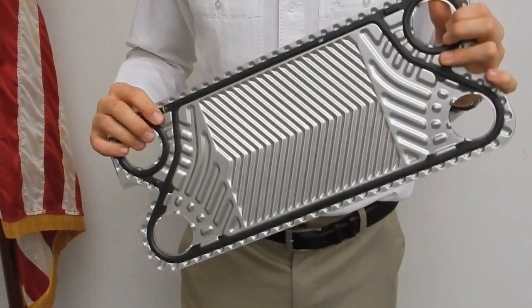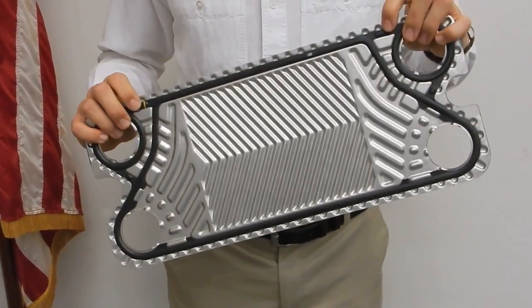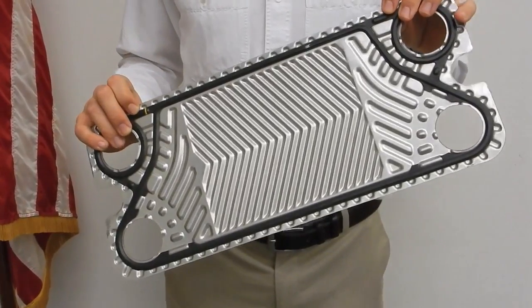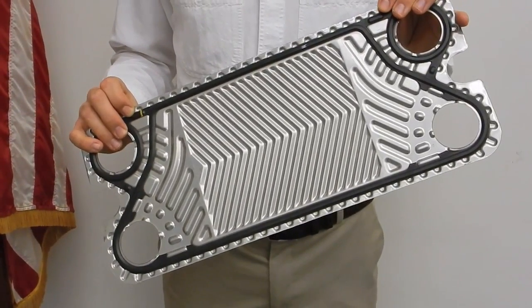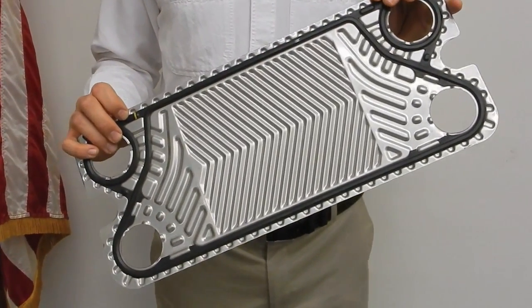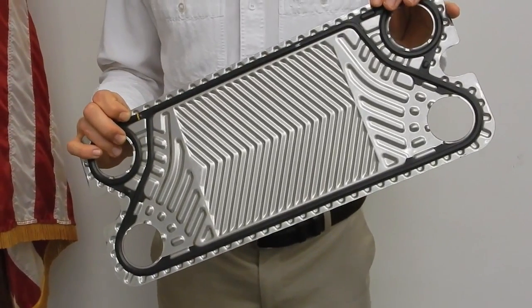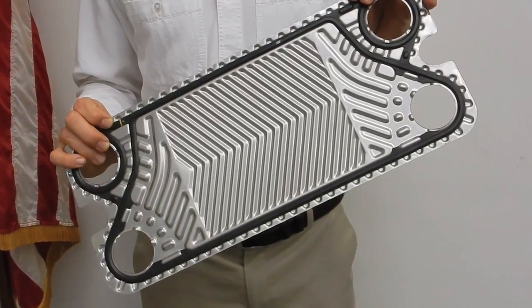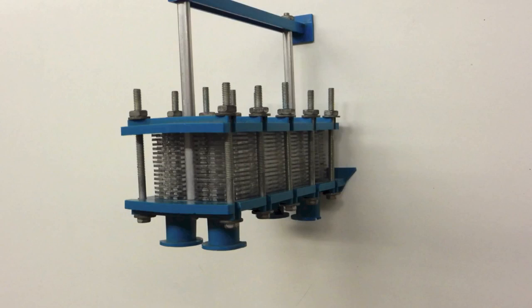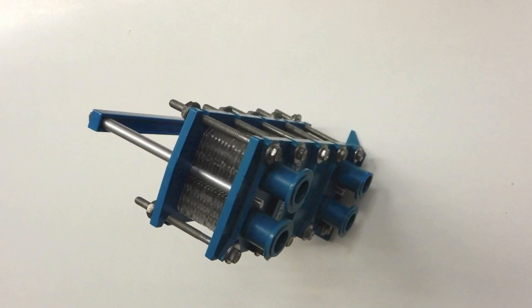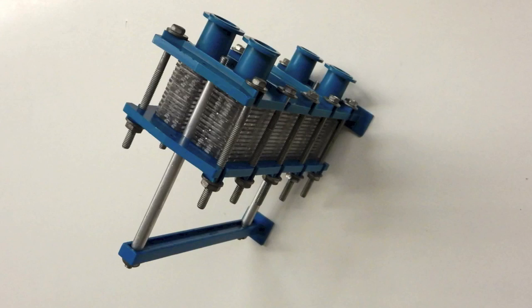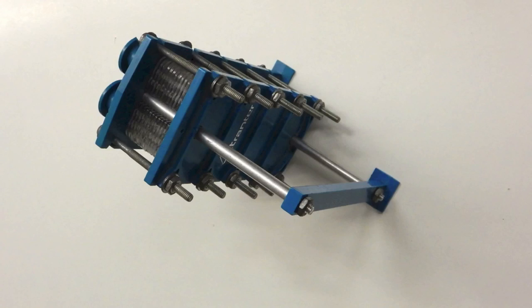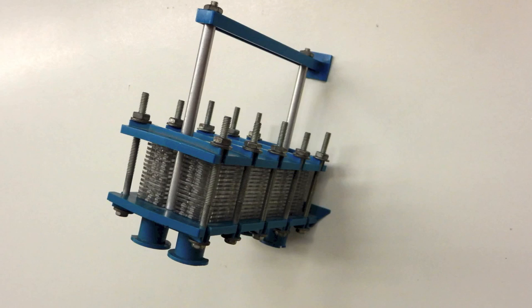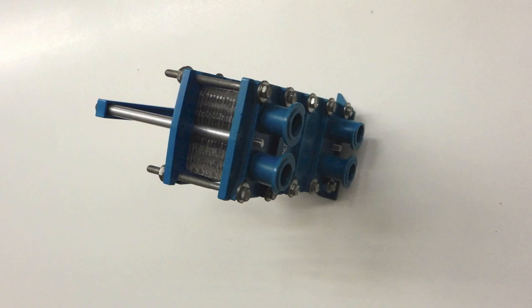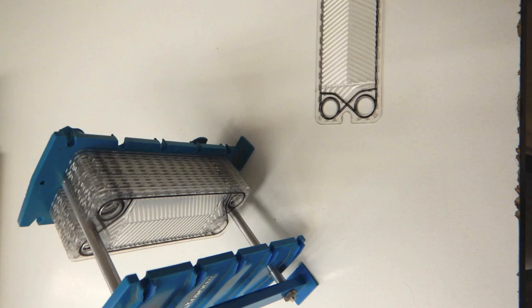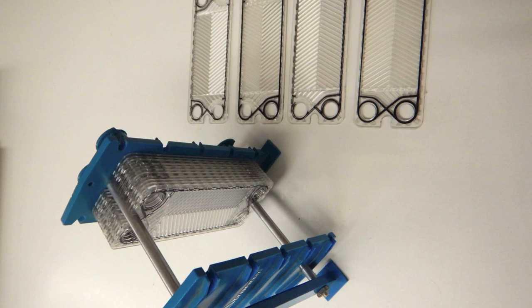The use of telltales means that at the first point of failure in a plate's gasket, the fluid is allowed to leak to the exterior of the heat exchanger. Thus, the system's condition can be visually checked without having to stop operations or dismantle it. Plate-type heat exchangers have faster startup times and are more compact in size than their shell and tube counterparts. The telltales in each plate provide protection from fluid contamination, as there must be two separate failures in the gasket in order for the two fluids to come in contact with one another.